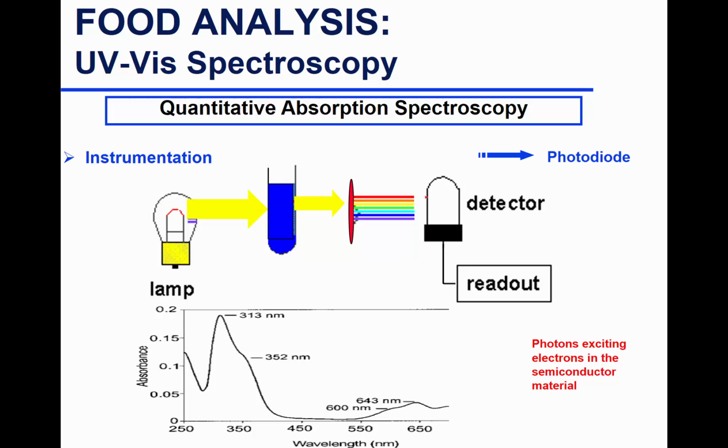All right, so a photodiode array, we talked about that for HPLC. What it does, it generates a spectrum. So in this case, the diffraction of light doesn't occur first. All the light gets projected to your sample, and then after that, the transmitted light gets diffracted. And then you have multiple wavelengths hitting the detector, and you get simultaneous absorption at different wavelengths, at a broad range of wavelengths.